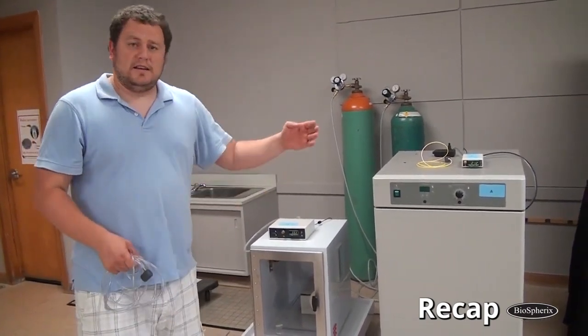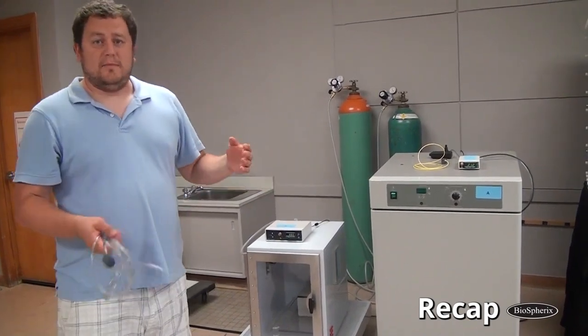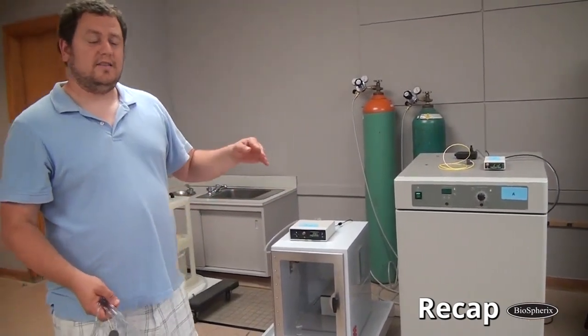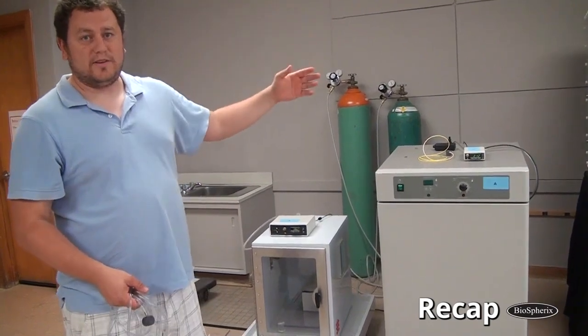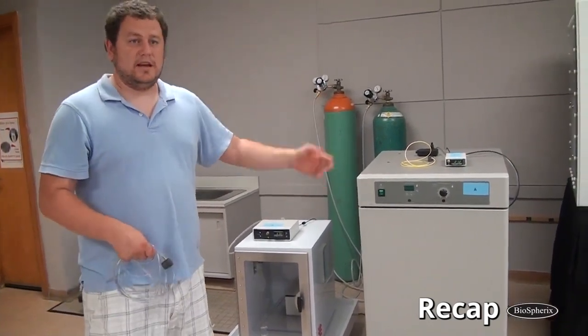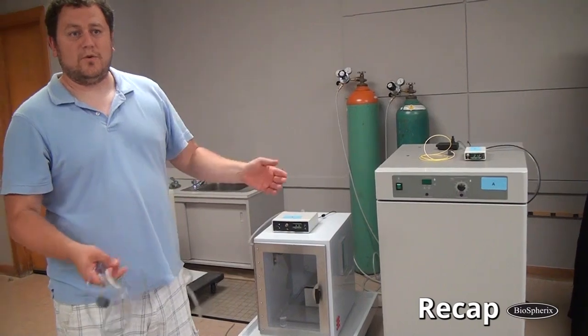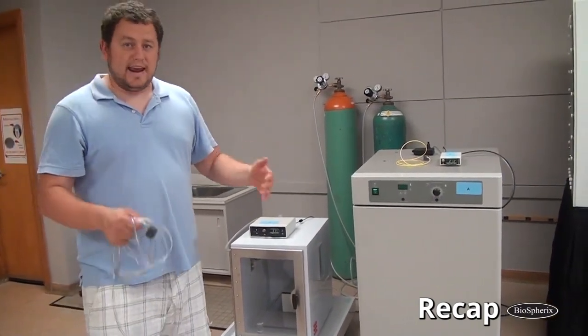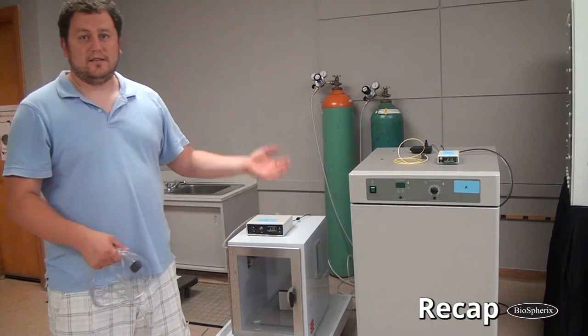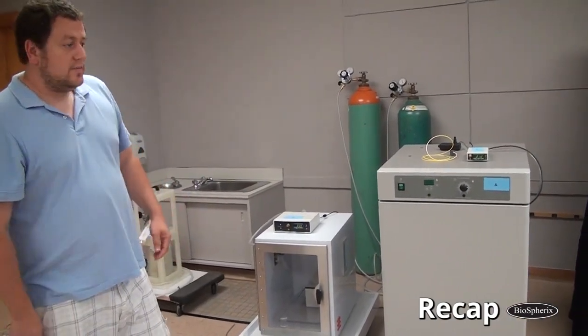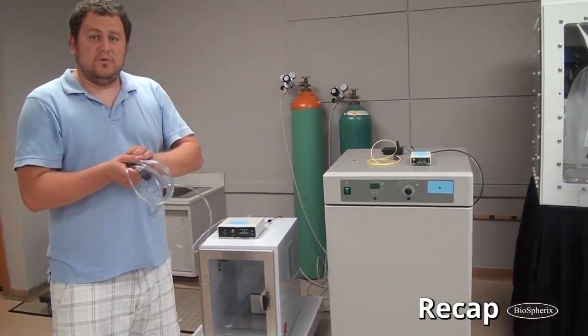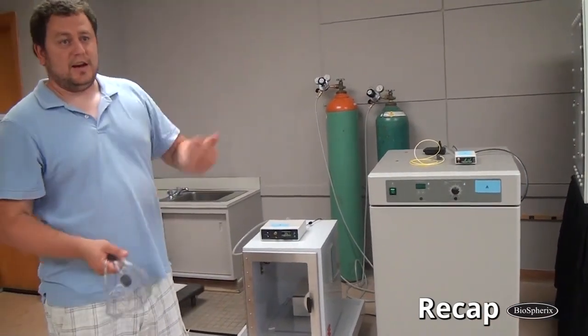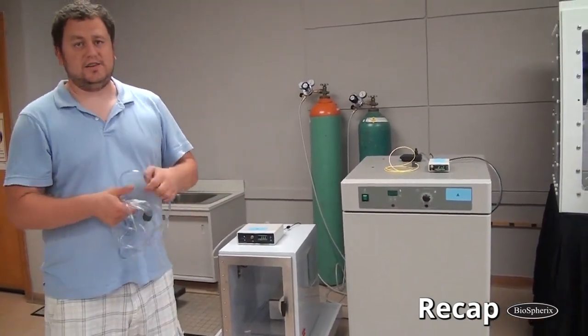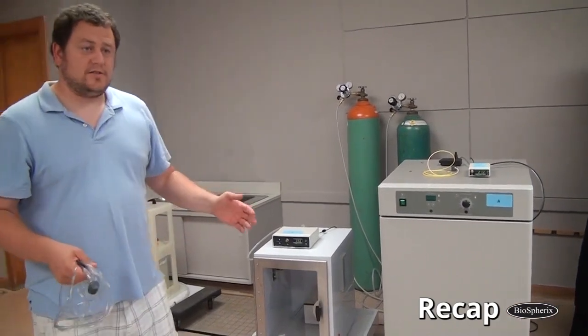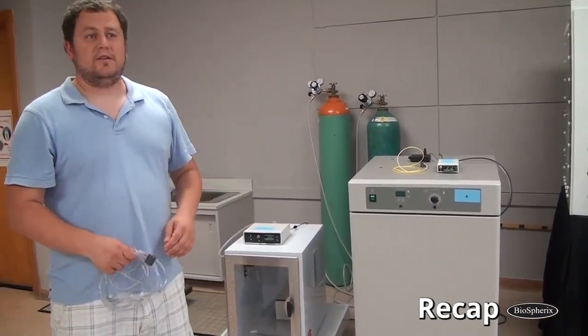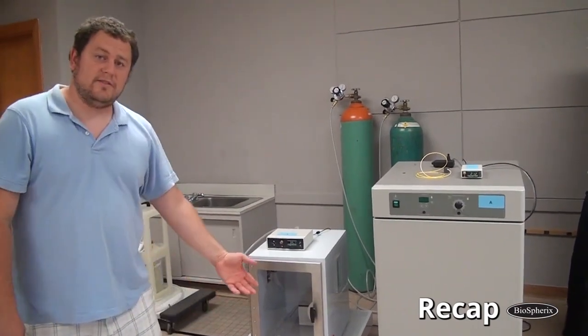The span on a brand new sensor usually starts in the -60s somewhere, and it typically gets more positive over time. So when you see your sensor start reading -40, -30, -20, that lets you know your sensor has aged significantly, and that's a good idea to change that sensor out. If you see it do really big jumps each time you calibrate, that's also showing that it's aged. Again, every sensor is different, and there are sensors out there, it's rare, that get more negative over time.